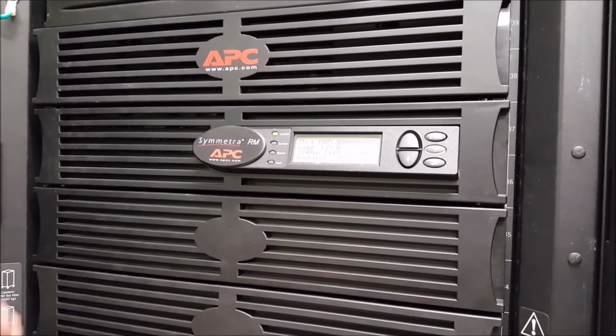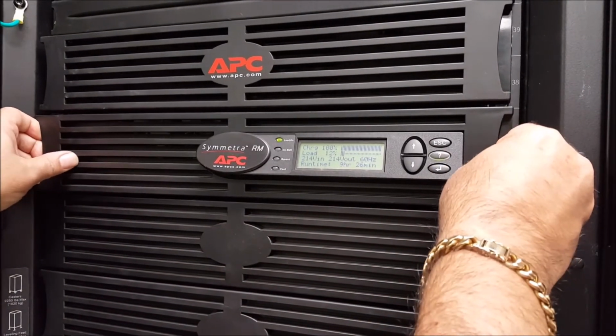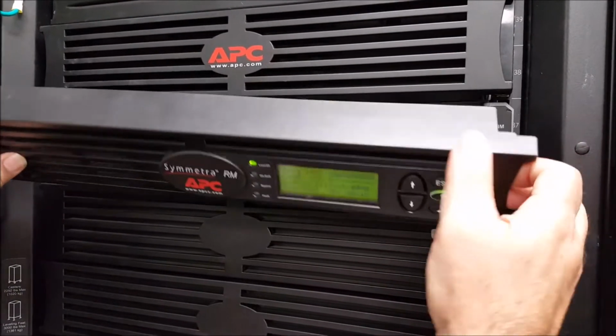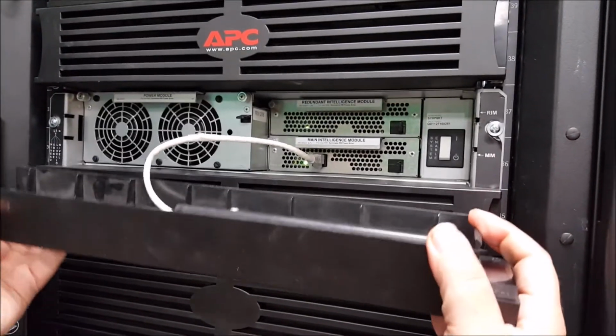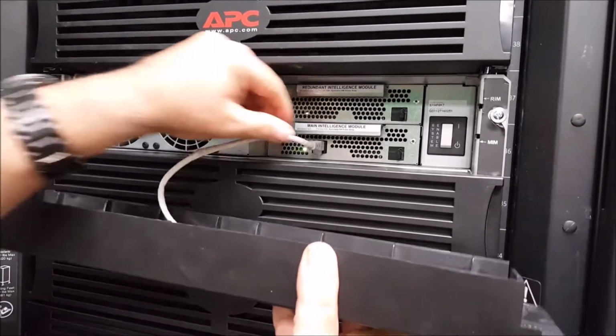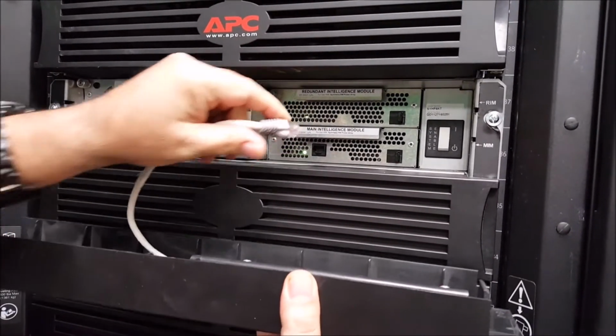To perform a full power down of a Symmetra RM unit, you first want to make sure that any attached loads such as servers are powered down correctly. Next, you'll want to remove the front bezel cover on the Symmetra RM. It'll probably be a good idea to disconnect the Ethernet cable connecting the power view display to the intelligence modules.